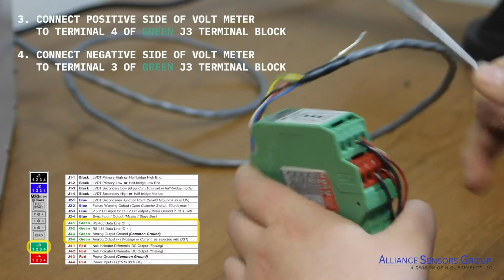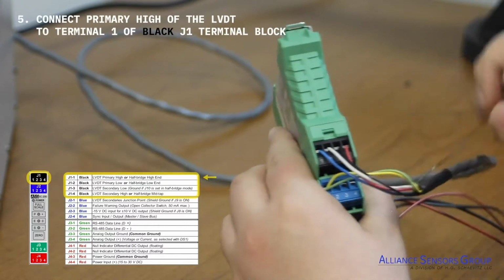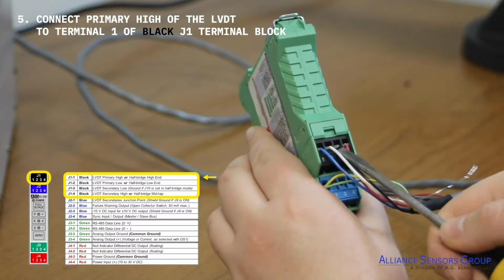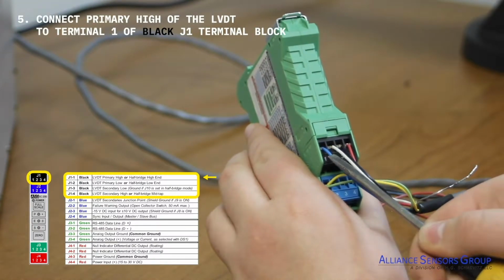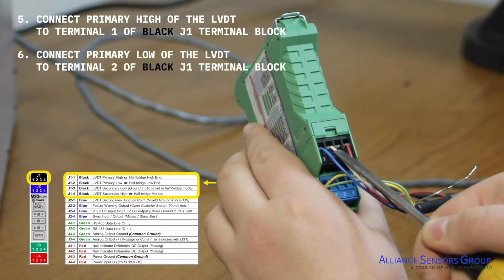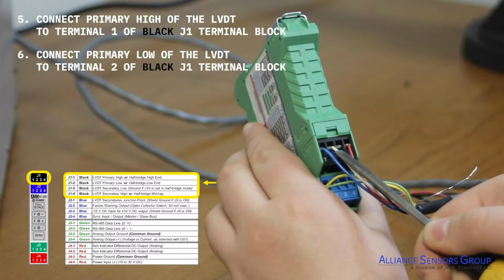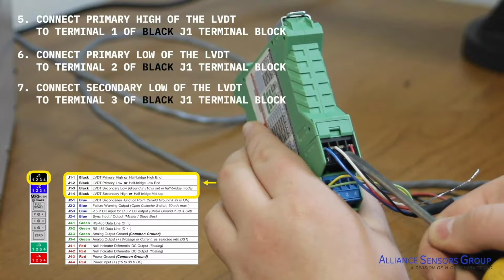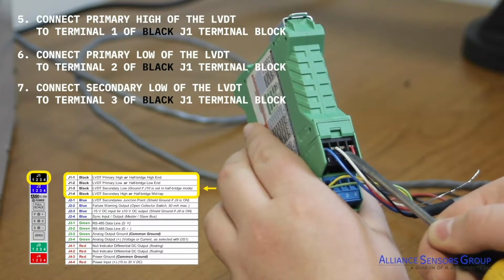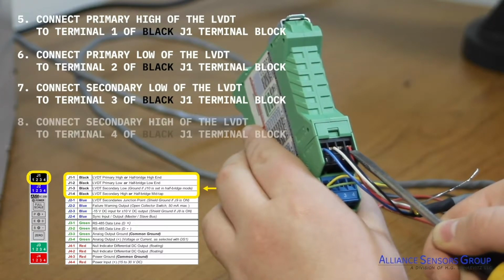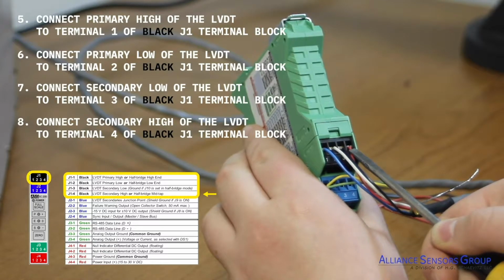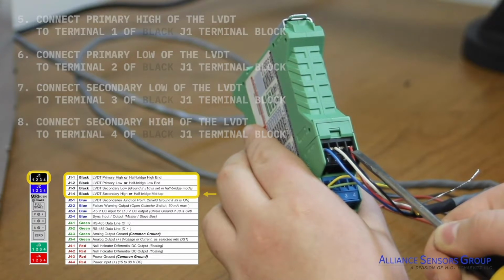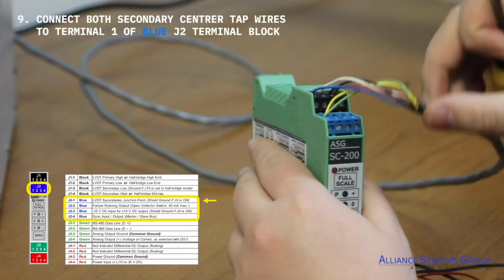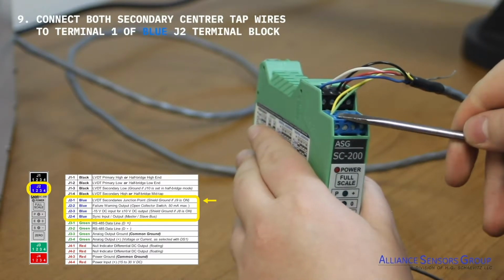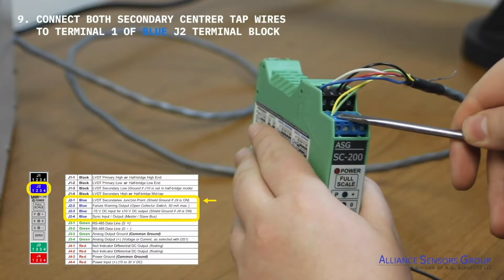When connecting the LVDT, attach the primary high of the LVDT to terminal 1 of the J1 black terminal block, and the primary low to terminal 2. Connect the secondary low of the LVDT to terminal 3 of the J1 black terminal block, and attach the secondary high to terminal 4. Both secondary center tap wires must be connected together and can be attached to terminal 1 of the J2 blue terminal block for convenience.